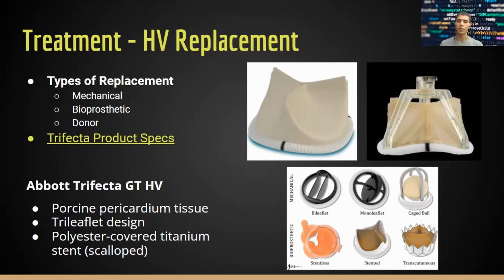One of the pluses is that it provided satisfactory blood flow for being one of the early prototypes, but it involved other complications such as lysing of blood cells, of hemoglobin, and accelerated clotting. So you don't want that on your device. Further developments include the monoleaflet and bileaflet mechanical heart valves, which are made of pyrolytic carbon to prevent clotting on the device. Bioprosthetic heart valves are usually taken from porcine or bovine tissue in animals, and they're sutured or sewn together in a way that simulates the native shape.